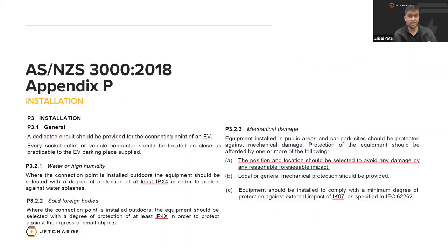So, installation. When we look at a dedicated EV charging station, we have to provide a dedicated circuit that's rated at the capacity of the EV charger. A 7 kilowatt charger will be a single phase 32 amp dedicated circuit, and 22 kilowatts will be three phase 32 amps. Every socket outlet should be located as close as practically possible to the EV charging space, because cables typically don't go past 10 meters before they have difficulties with connection and usage. They typically have a minimum of IP44 rating so that they are protected against humidity, water, and dust.